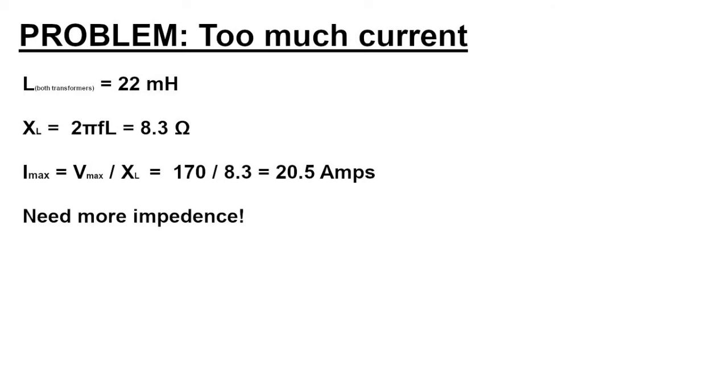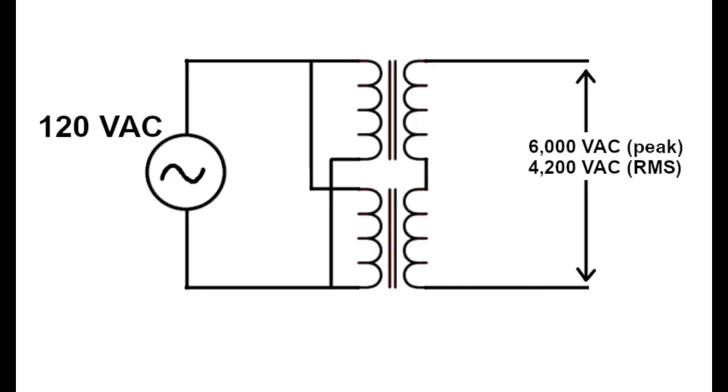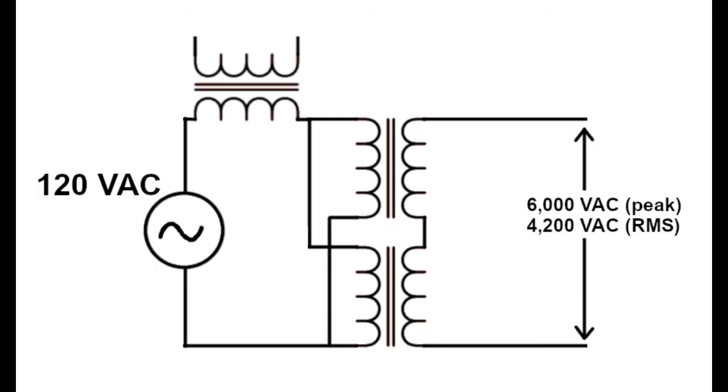So we need a bigger source of impedance. Going back to the original schematic, what I'm going to do is add a third transformer in series with the circuit, but I'm not going to connect the other side to anything. What the third transformer does is it adds inductance in series with the whole circuit to increase the impedance and reduce the current.